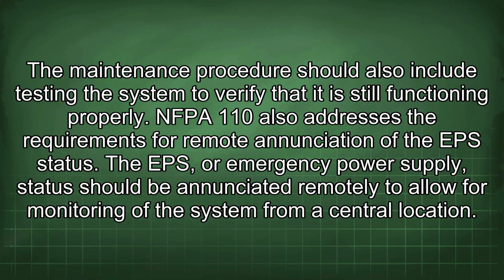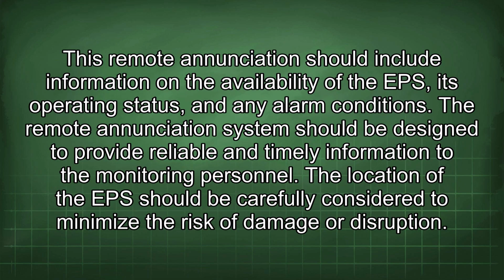NFPA 110 also addresses the requirements for remote annunciation of the EPS status. The EPS, or Emergency Power Supply, status should be annunciated remotely to allow for monitoring of the system from a central location. This remote annunciation should include information on the availability of the EPS, its operating status, and any alarm conditions. The remote annunciation system should be designed to provide reliable and timely information to the monitoring personnel.